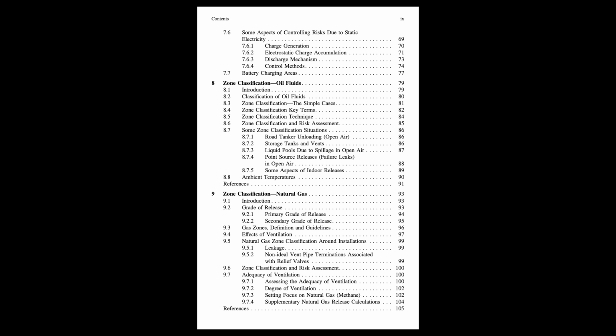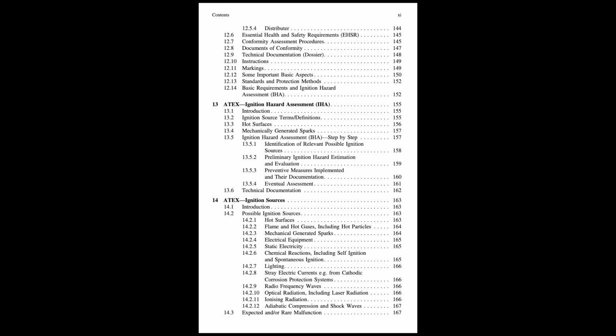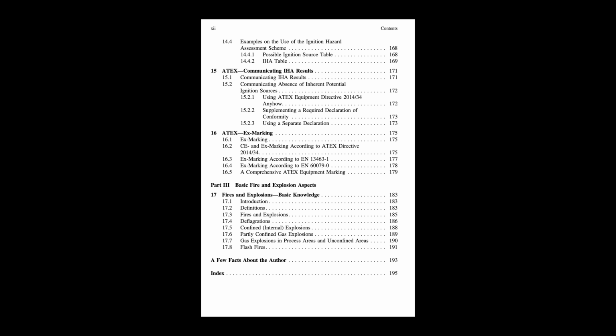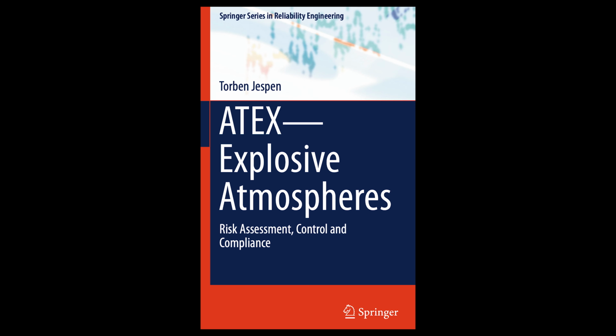Now, you mentioned the ignition hazard assessment, IHA, again, particularly for non-electrical stuff. The guide details this. What's the main goal of an IHA? The IHA's purpose is to systematically scrutinize a piece of equipment, usually mechanical, but sometimes electrical components too, to identify all potential ignition sources it might contain or create. Then, based on how likely those sources are to become active, you determine the correct ATEX equipment category for it. So it's a deep dive into the equipment itself. Exactly. Looking for anything that could get hot, create a spark, mechanical, electrical, static, or otherwise ignite a surrounding explosive atmosphere. It distinguishes between inherent sources, potential sources that need certain conditions, and effective sources likely to cause ignition.